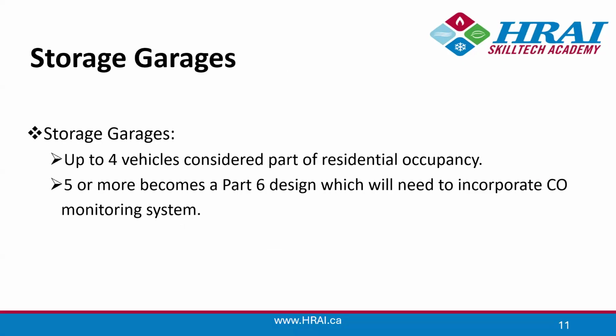Another big change would be in the storage garages. In the past, we would say you could have up to 5 vehicles or 5 parking spaces indoors and be considered following Part 9 as it is, but now that number's been reduced to 4.